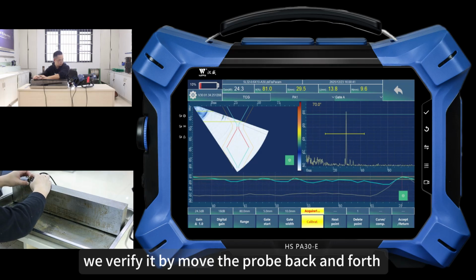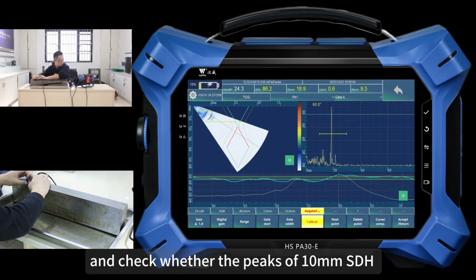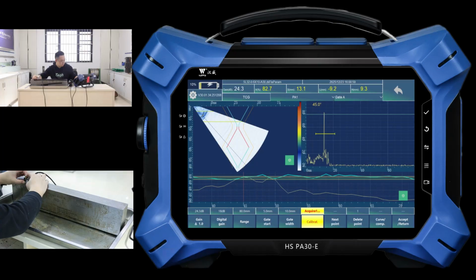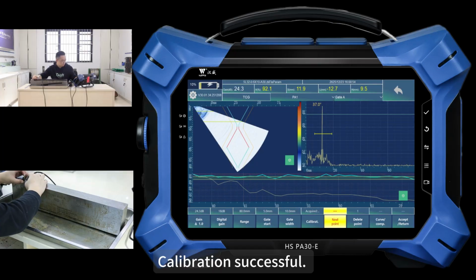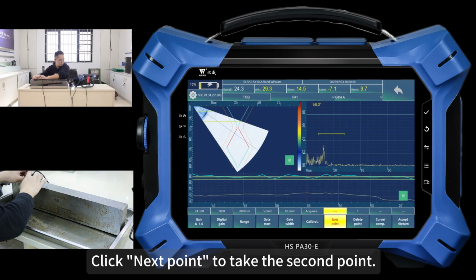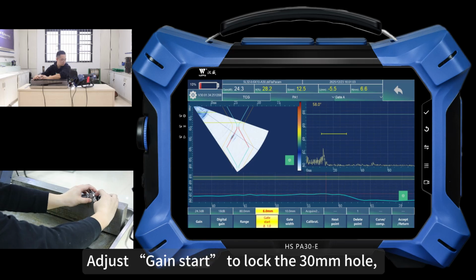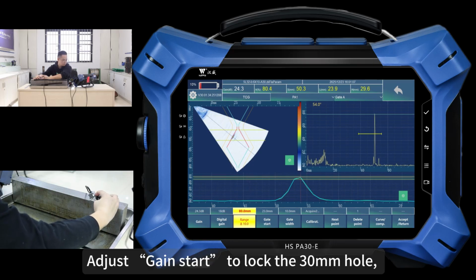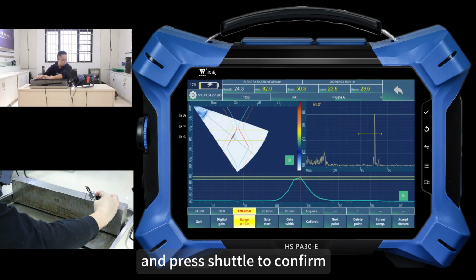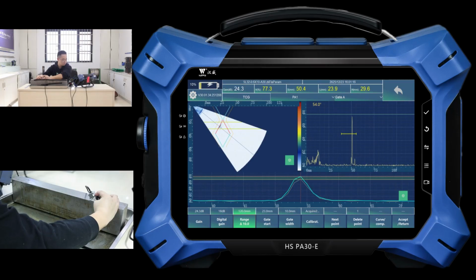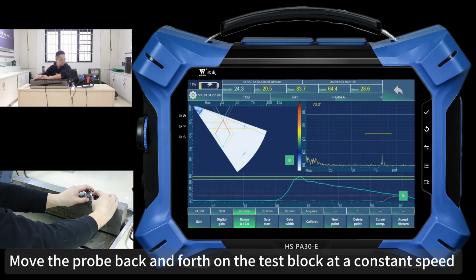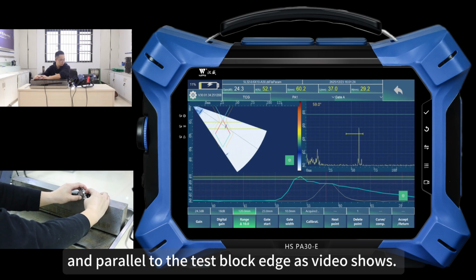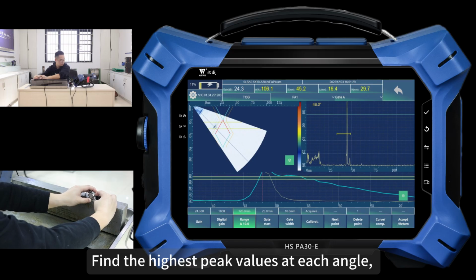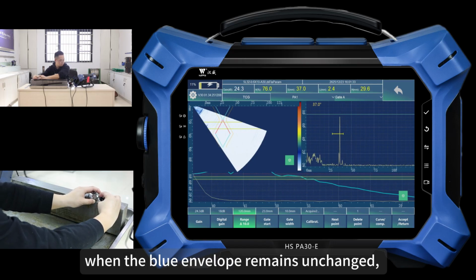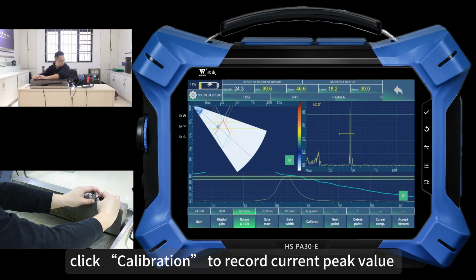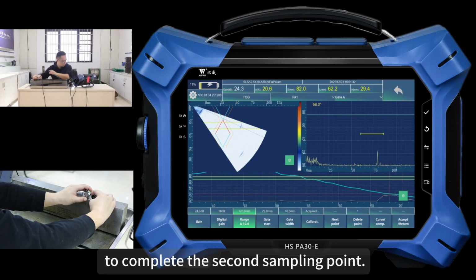After taking the first point, we verify it by moving the probe back and forth and checking whether the peaks of the 10 mm SDH are within the 2 yellow lines. Calibration successful. Click Next Point to take the second point. Adjust gate start to lock the 30 mm hole, adjust range to an appropriate value and press shuttle to confirm. Move the probe back and forth on the test block at a constant speed and parallel to the test block edge as the video shows. Find the highest peak values at each angle when the blue envelope remains unchanged. Click Calibration to record the current peak value and then click OK to complete the second sampling point.